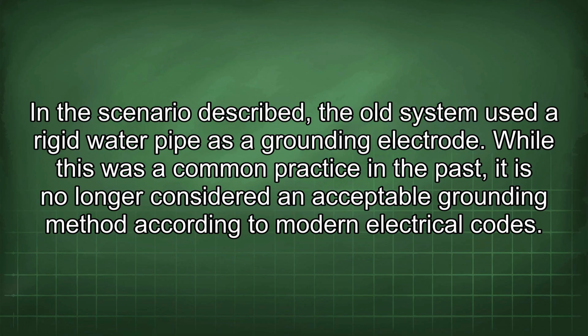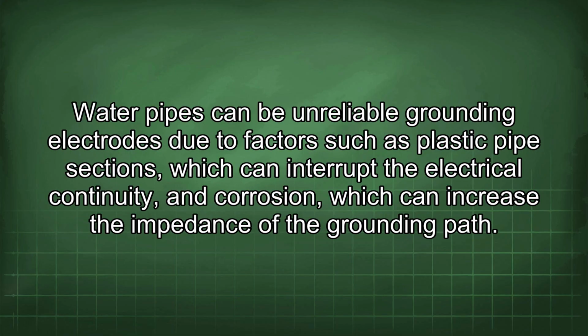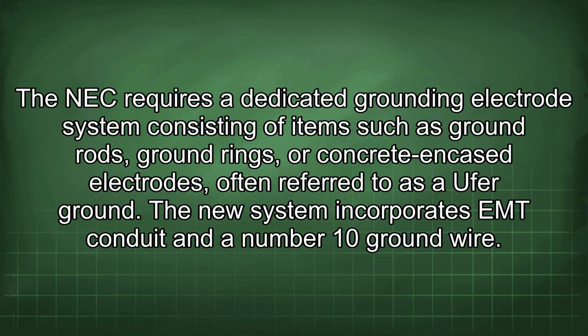In the scenario described, the old system used a rigid water pipe as the grounding electrode. While this was common practice in the past, it is no longer considered an acceptable grounding method according to modern electrical codes. Water pipes can be unreliable grounding electrodes due to factors such as plastic pipe sections, which can interrupt the electrical continuity, and corrosion, which can increase the impedance of the grounding path. The NEC requires a dedicated grounding electrode system consisting of items such as ground rods, ground rings, or concrete encased electrodes, often referred to as a Ufer ground.